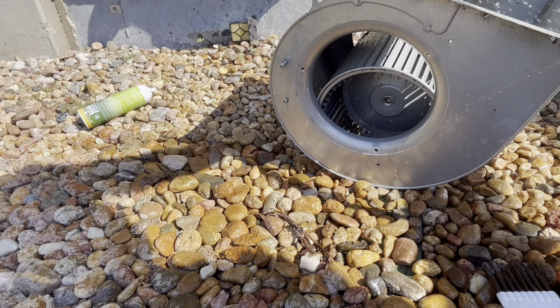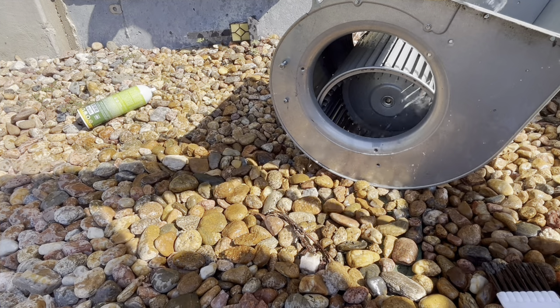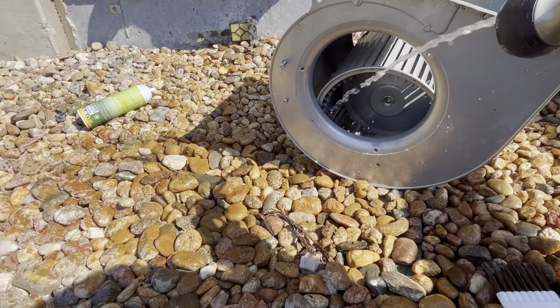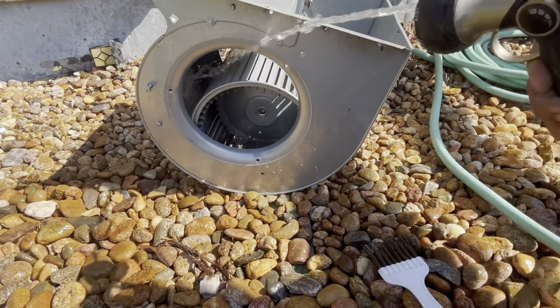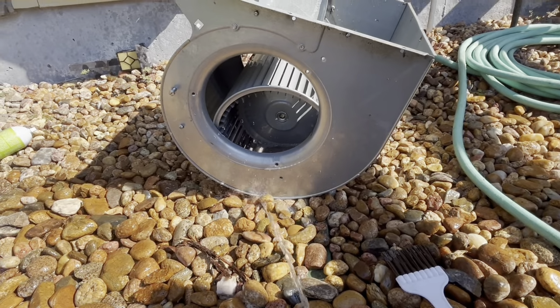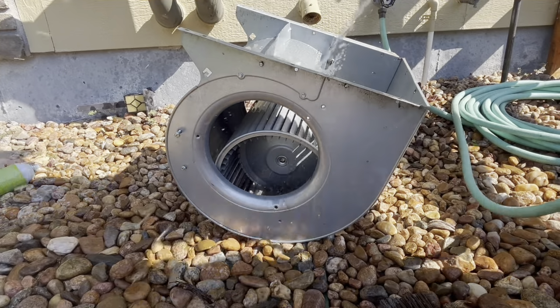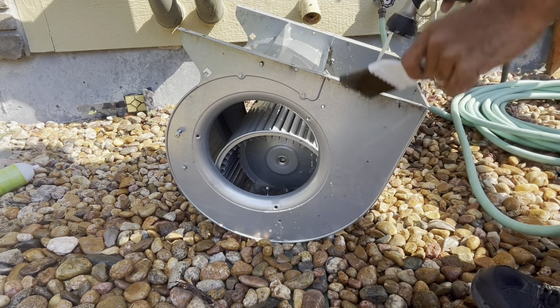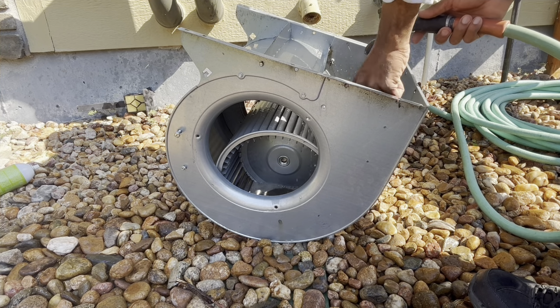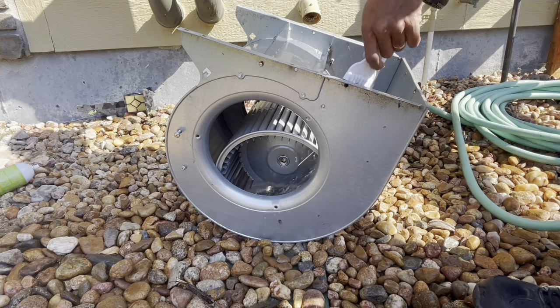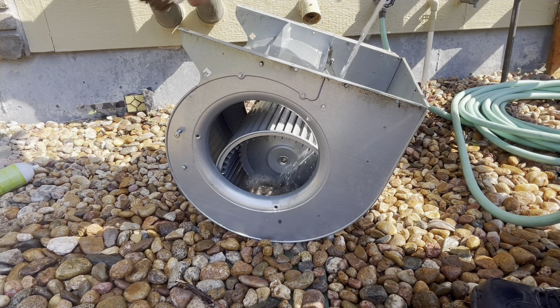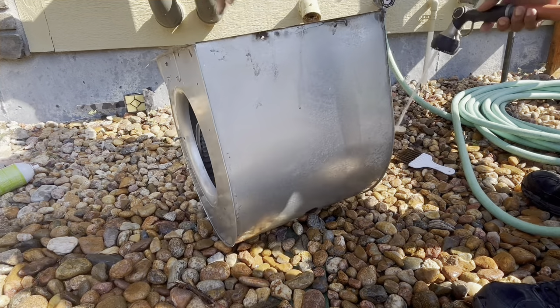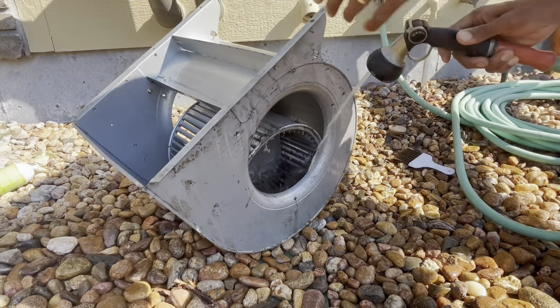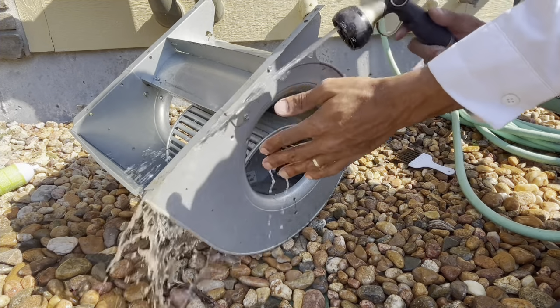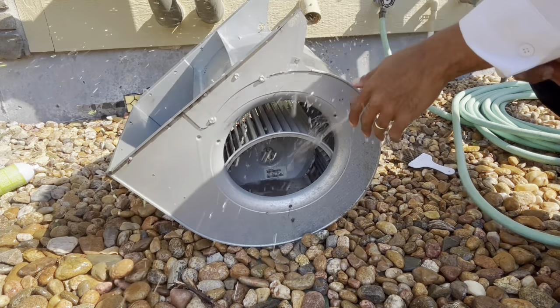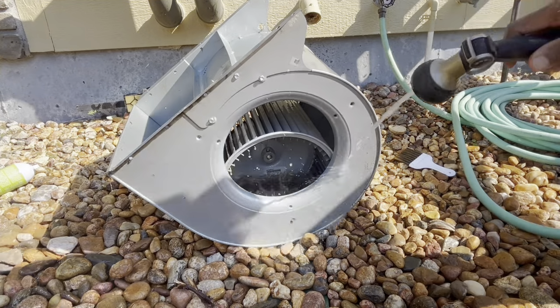So after everything soaks for 5-10 minutes or so, just go through with a water hose, connect it up to the house, and I set the nozzle to the jet spray to get as much force of the water out, to basically get it clean. And you can see in the pictures or this video where it actually becomes quite clean for the most part. If it's just normal dirt and debris, it comes clean. If it's a motor that's been leaking oil for quite some time, those are harder to clean, because then all the dirt and debris sticks to the oil, and the oil sticks to that blower housing. It's all over the wheel. It's just a mess at that point. So it takes like twice as long to clean it.